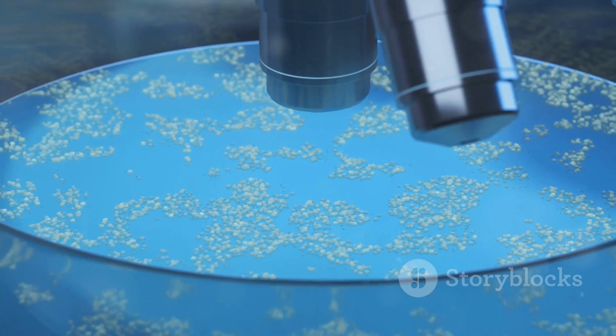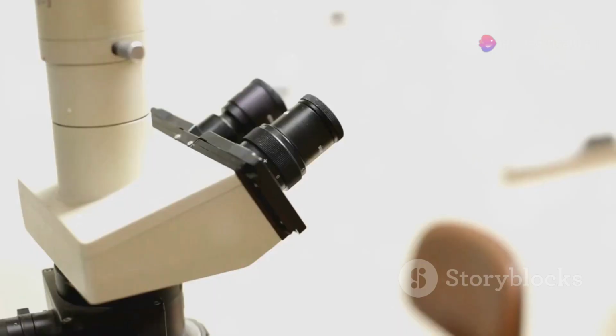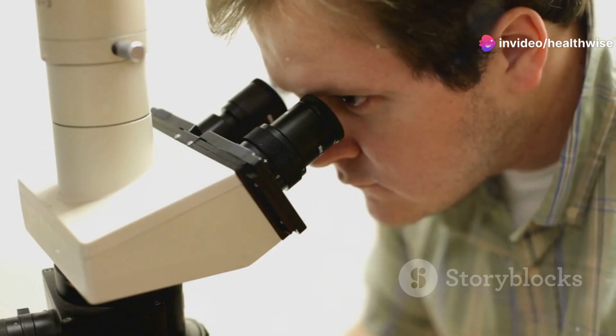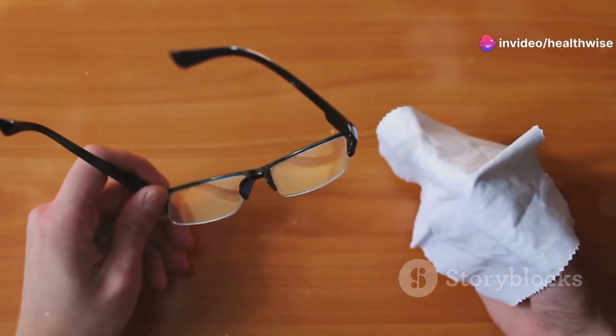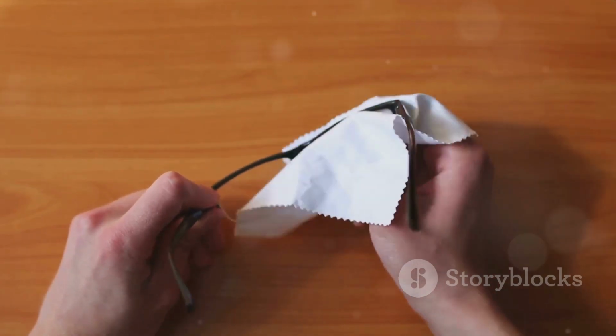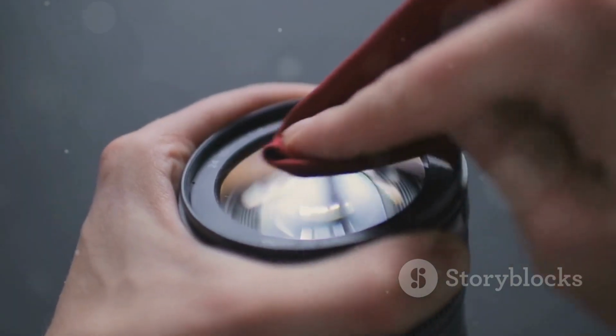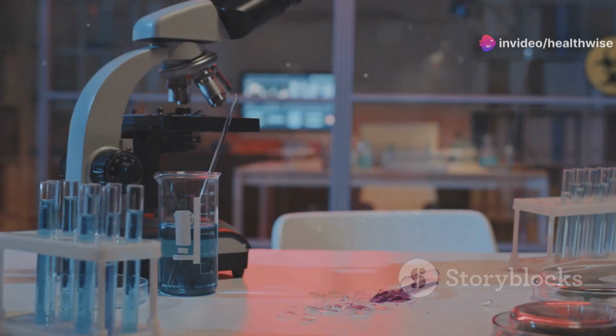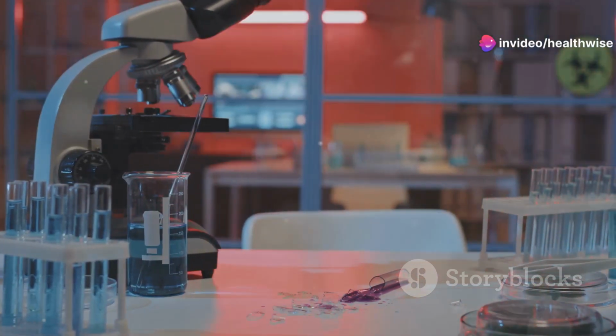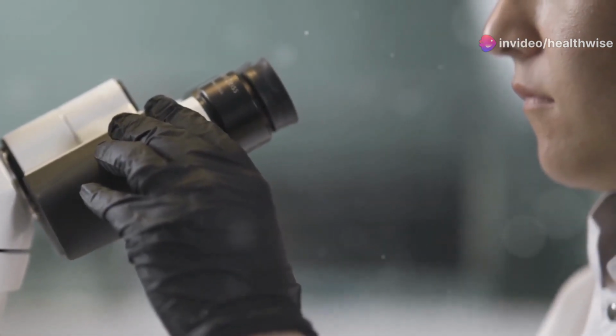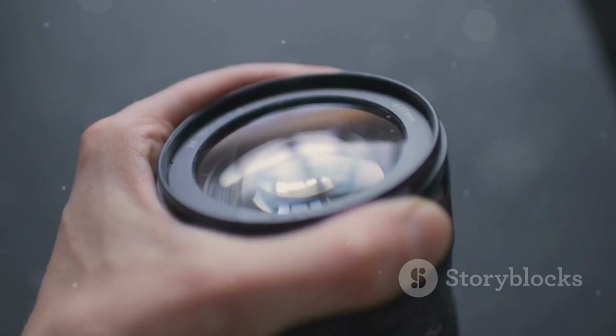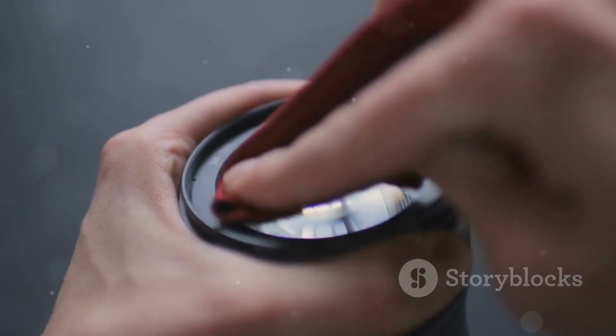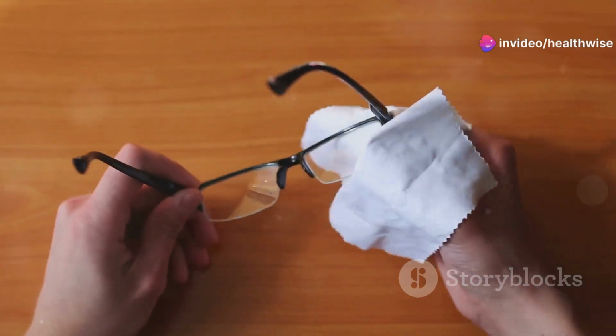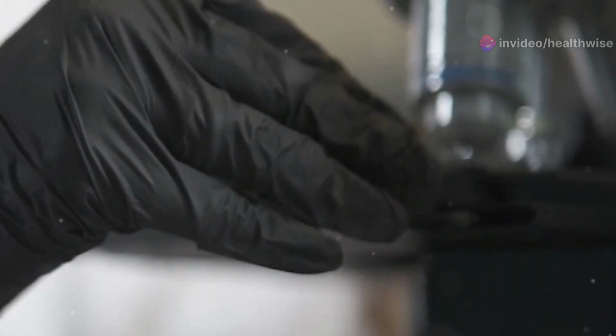The eyepieces, those portals through which we peer into the microcosmos, are our direct link to the magnified world. Just like a telescope's eyepiece, keeping them clean ensures a clear and unobstructed view of the microscopic realm. Dust, debris, and even eyelash oils can accumulate on the eyepiece surface, creating distractions and diminishing the quality of your observations. Thankfully, maintaining the pristine clarity of your eyepieces is a straightforward process. Begin by gently blowing away any loose dust particles from the eyepiece surface. Then, using a piece of soft, lint-free tissue paper, gently wipe the eyepiece in a circular motion. Avoid excessive pressure, as this could potentially scratch the delicate lens surface.